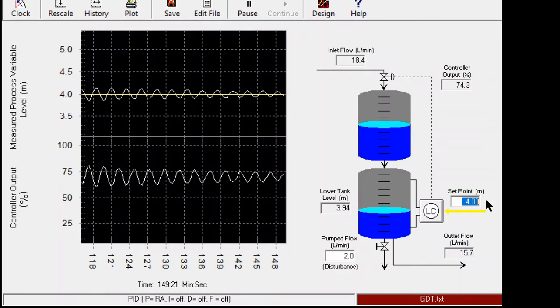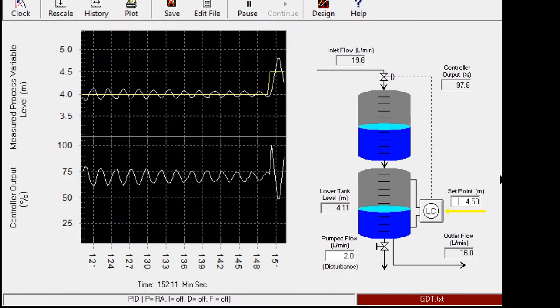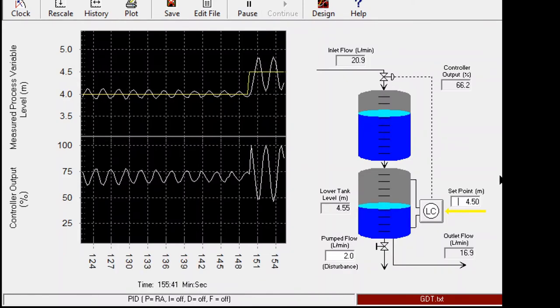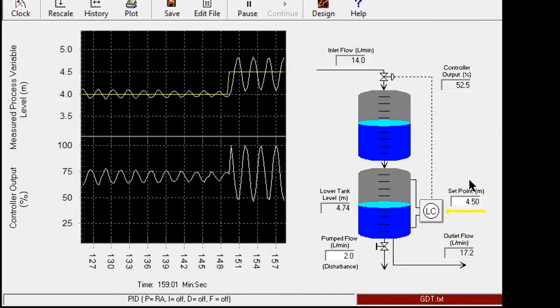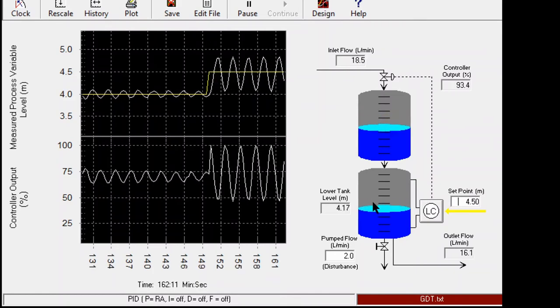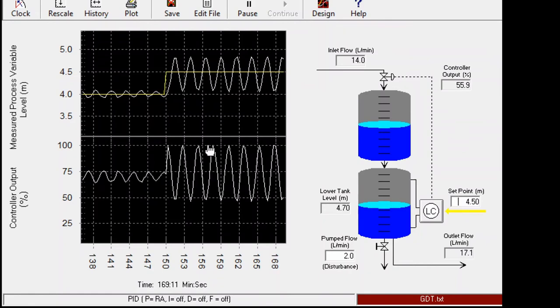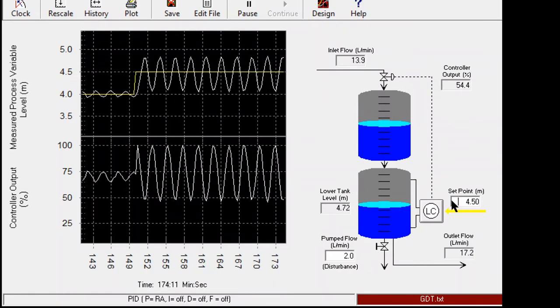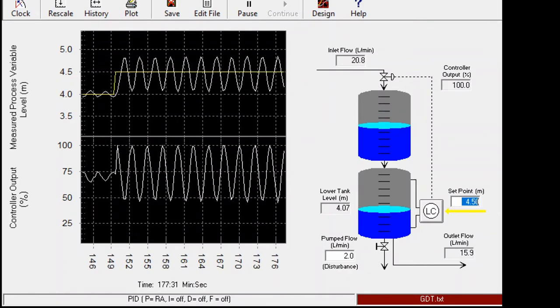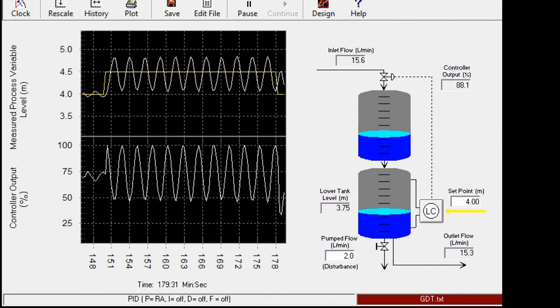And now if I make it from 4 to suppose 4.5, we see that the oscillation looks like sustained, however it's reaching the valve saturation. So we'll see whether without reaching valve saturation we can get something oscillating or not. So again bring it back to 4.